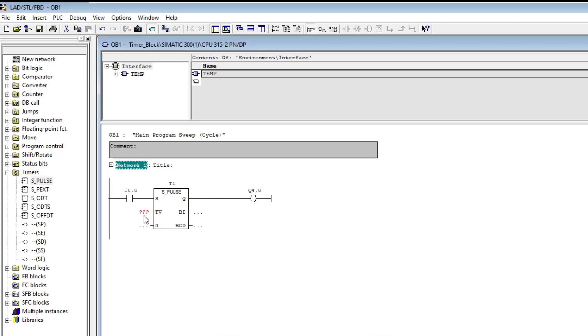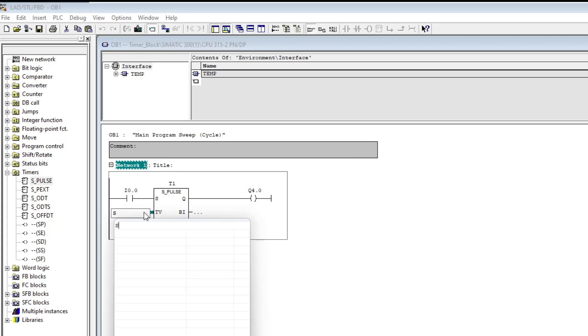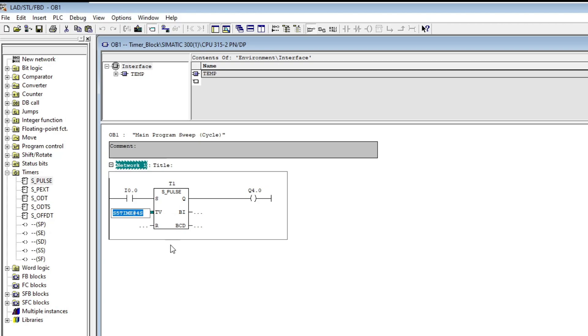The input called TV stands for time value. The TV input is used to specify the duration or the time value for the timer. To set a time value we write S5 time hashtag followed by how long we want it to count for.